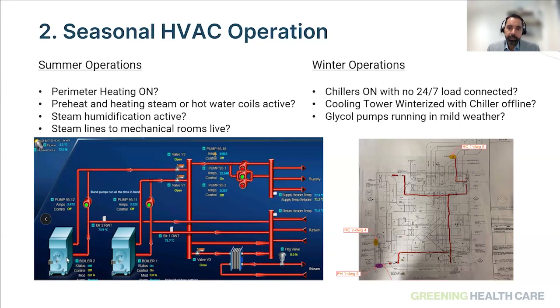The chiller energy tends to be higher on those hospital sites where the perimeter heating is on, especially when the preheat and heating steam coils are also active in the summertime, because a lot of the time there are passing valves on these coils, which end up resulting in heat being picked up by the chilled water and eventually going back to the chiller plant. So sometimes in some of these facilities, they have tapped out on the chillers, because a lot of that chiller energy is actually going into cooling that extra heat that's been added by these systems.